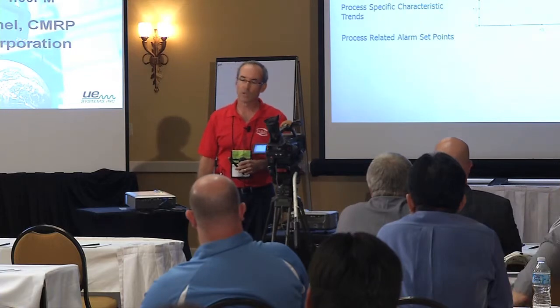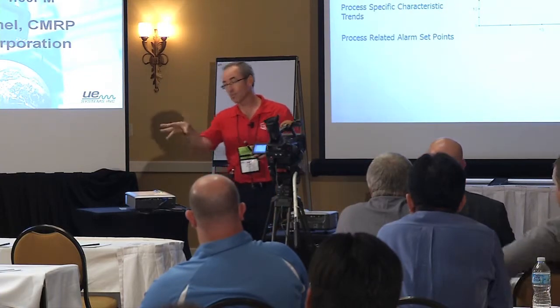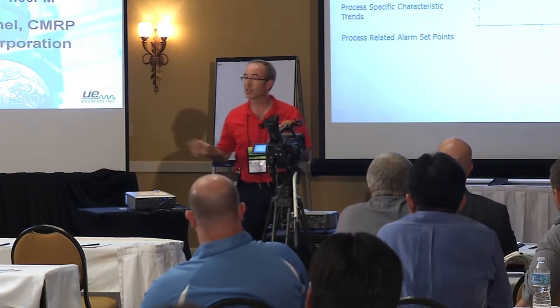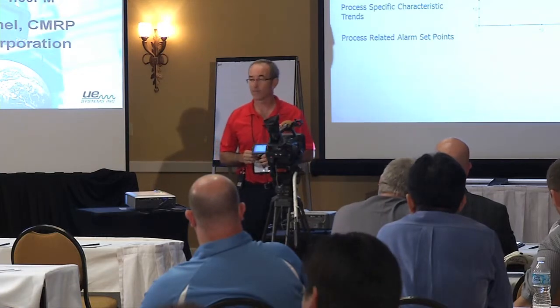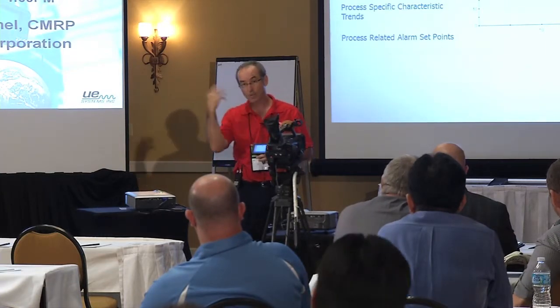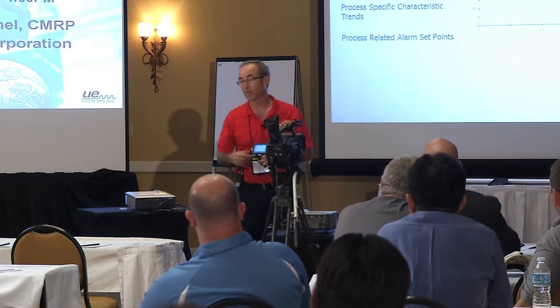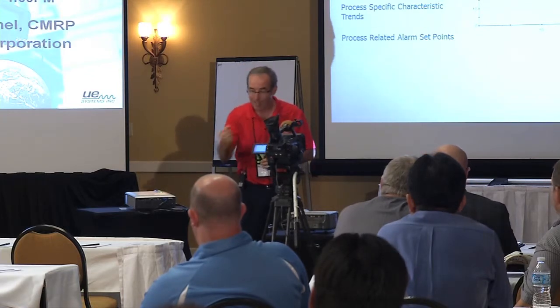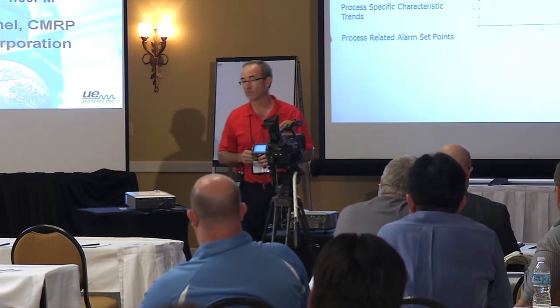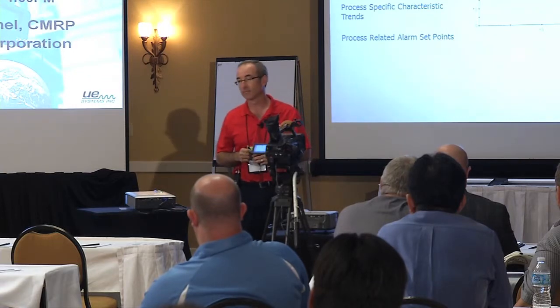So as comfortable as we are saying whether it's the motor or the drive—and that's pretty easy for us now—we could take it a step further. A lot of the mechanical analysis we talked about today is less effective on a variable frequency drive, because we're not sampling at a frequency optimized for, say, a 43 hertz drive.